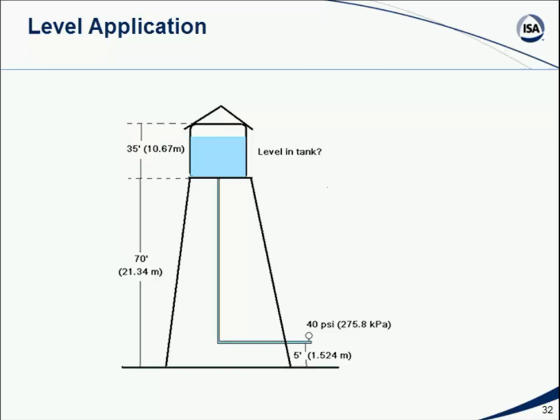But so our tank level is going to vary up and down by 35 feet. What we're going to measure at ground level, or 5 feet above ground level, shall we say, will be a fluid column of 65 feet up to 65 plus 35 feet. Right? So we're going to be measuring that pressure differential. Since this is water, we already know that the height of a column of water in feet is proportional to the pressure that we're measuring and the specific gravity of the fluid, which is, of course, 1 because it's water. So if we can take a pressure measurement, we can actually compute the height of the tank.